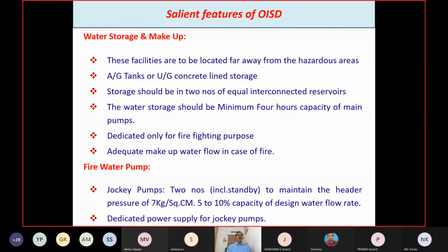So in the fire water pump house, jockey pumps should be provided, one for operation and one for standby, to maintain the header pressure of 7 kg per cm square. They should be designed for 5 to 10% of the capacity of the design water flow rate, and a dedicated power supply should be provided for the jockey pumps.